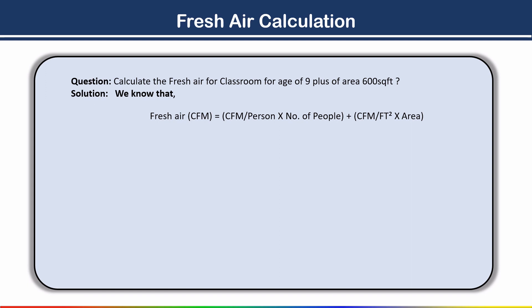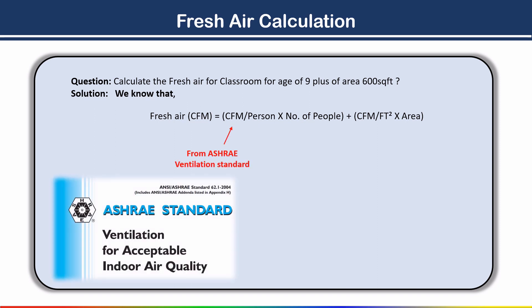The CFM per person value you get from the ASHRAE ventilation standard — I will show you the table from where we take this value. For number of people: first, check the furniture layout in the architectural drawing. If a furniture layout is given in the classroom, decide the number of people from that. Otherwise, ask the architect or interior decorator. If no detail is provided, from the ASHRAE ventilation standard you can also calculate the number of people as per area and space.